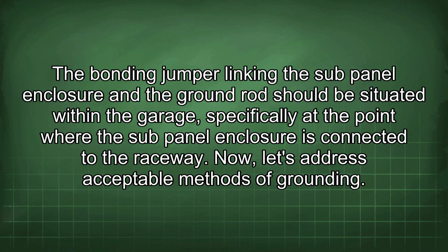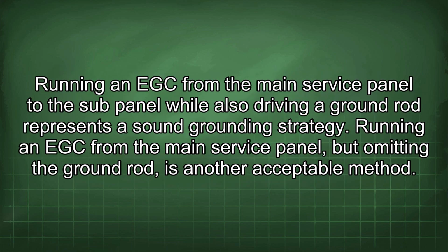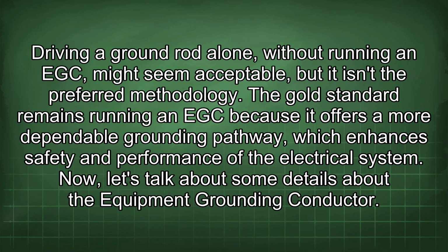Now, let's address acceptable methods of grounding. Running an EGC from the main service panel to the sub-panel while also driving a ground rod represents a sound grounding strategy. Running an EGC from the main service panel, but omitting the ground rod, is another acceptable method. Driving a ground rod alone, without running an EGC, might seem acceptable, but it isn't the preferred methodology. The gold standard remains running an EGC because it offers a more dependable grounding pathway, which enhances safety and performance of the electrical system.